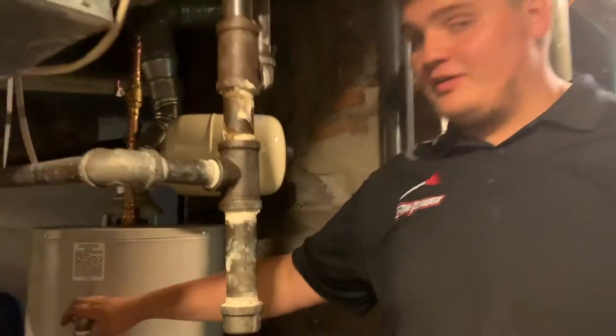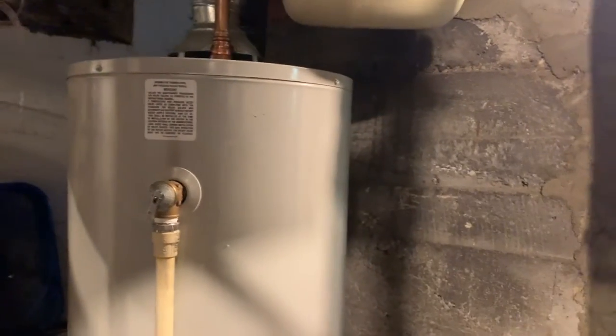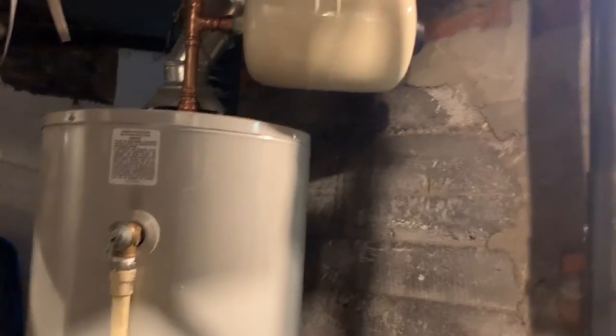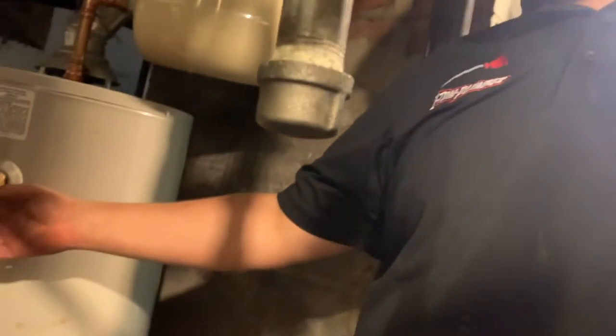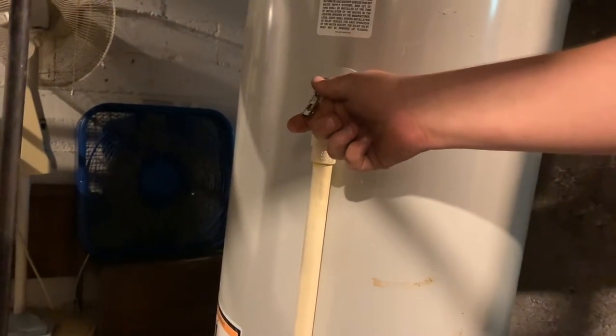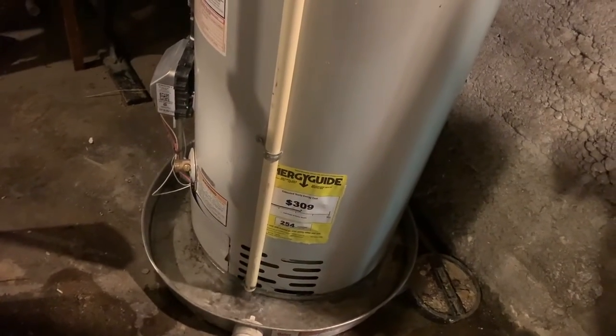Usually for the T&P valve — it stands for temperature and pressure — it should only go off when the temperature in the heater is too high or the pressure in your house is too high. Sometimes it does happen where if you nudge this little knob and the water comes out and it continuously leaks, a lot of the times all you need to do is just replace the T&P valve, and we will show you how to do that shortly.